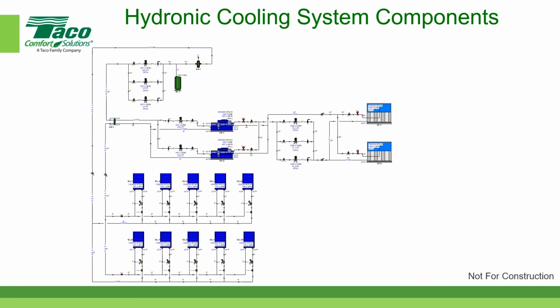Well, actually, that's an excellent, excellent question. The actual heat that is rejected as a function of the inefficiency of the chiller is probably going to translate into less than 3 GPM per ton. And you have to get that information from the chiller manufacturer. The reason we use 3 GPM per ton is because it covers a variety of sins. When water-cooled chillers were first used on commercial systems, they were quite inefficient, not as efficient as the newer chillers are today. And because of their inefficiency, the 3 GPM per ton became a nominal flow rate for sizing condenser water systems, including cooling towers.